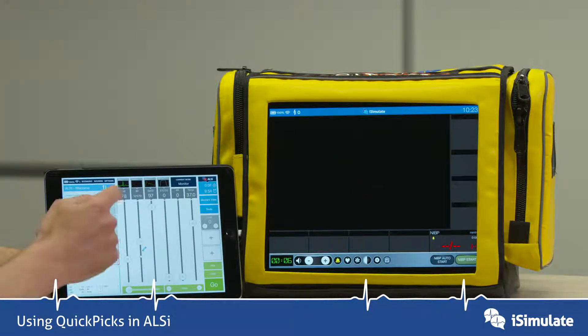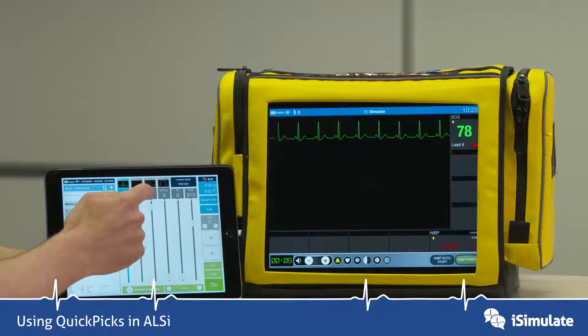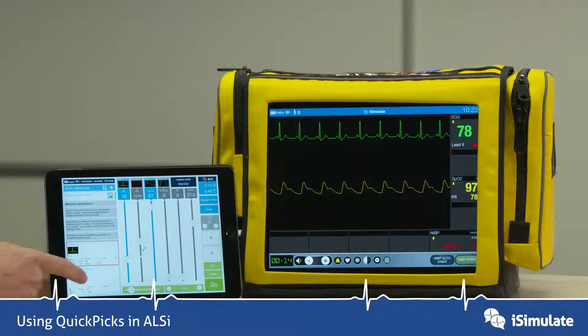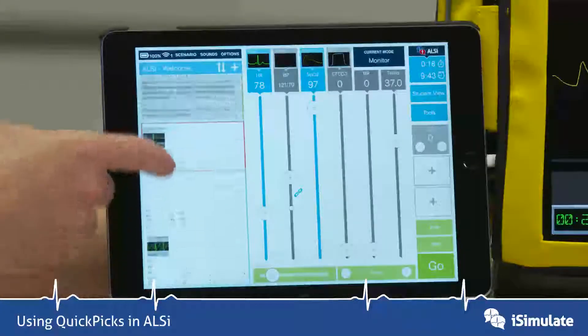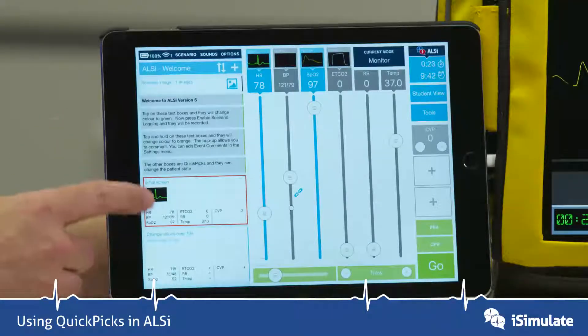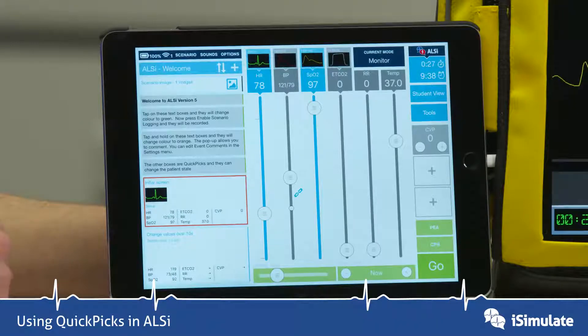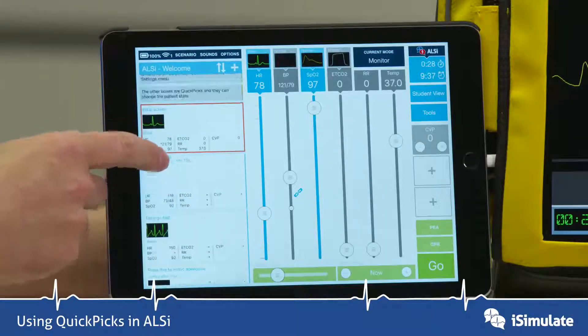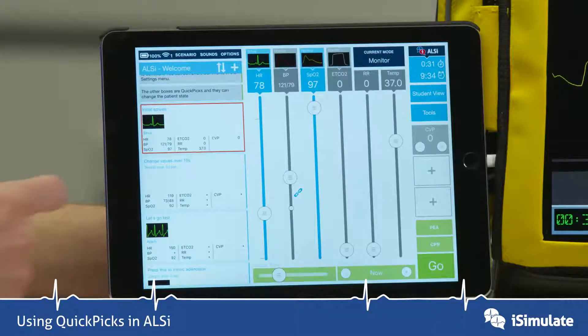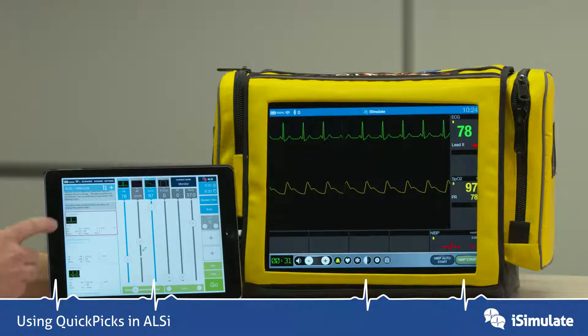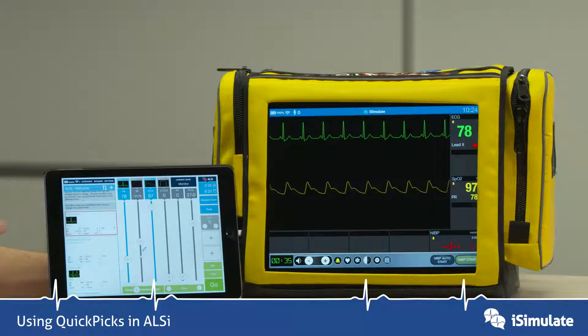Initially I'm going to turn on the heart rate and the SPO2. QuickPicks are down this left hand column and you can scroll up and down and you can see that there are boxes there. I'm going to concentrate on these parameter changing QuickPicks and also talk about the text boxes. This first QuickPicks is outlined in orange — that's the current active QuickPicks — and it shows that we've got a sinus rhythm with the various parameters that have been preset.